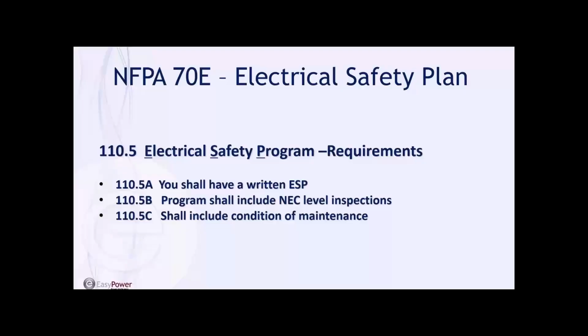110.5C says your electrical safety program shall include elements of condition of maintenance. If you take that further, you can scroll out to Chapter 2 of the 70E standard, which is safety-related maintenance and all its elements. It describes that although you need elements within your electrical safety plan related to condition of maintenance, it's a very broad understanding of the topics, priorities, frequencies, and various tests and procedures out there. So a facility has very broad latitude in what's included.